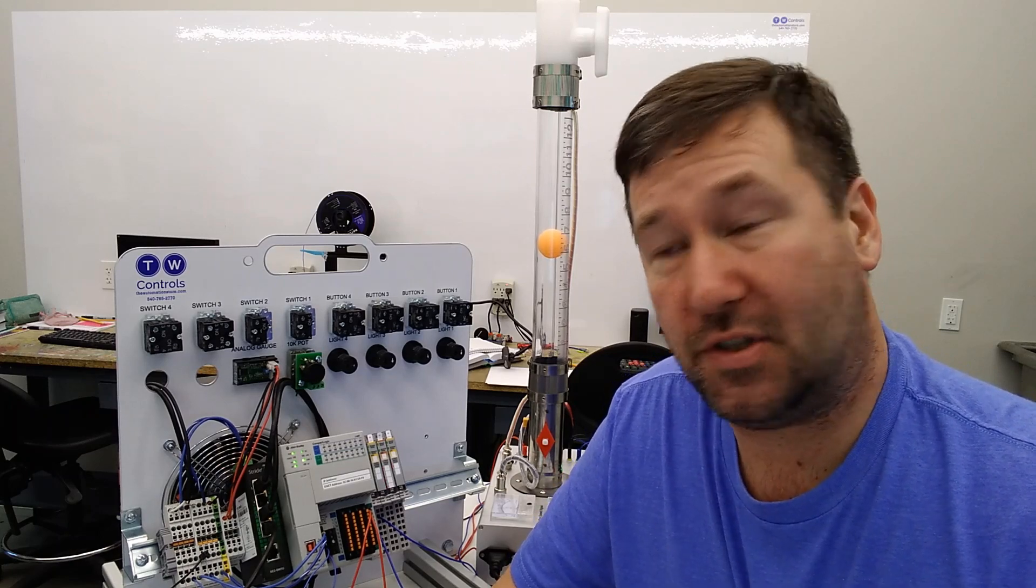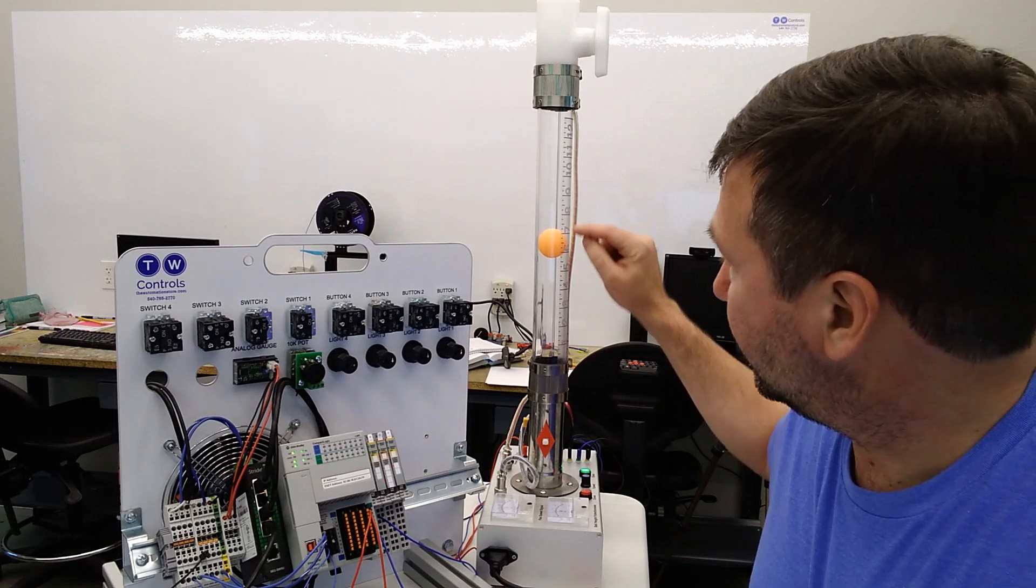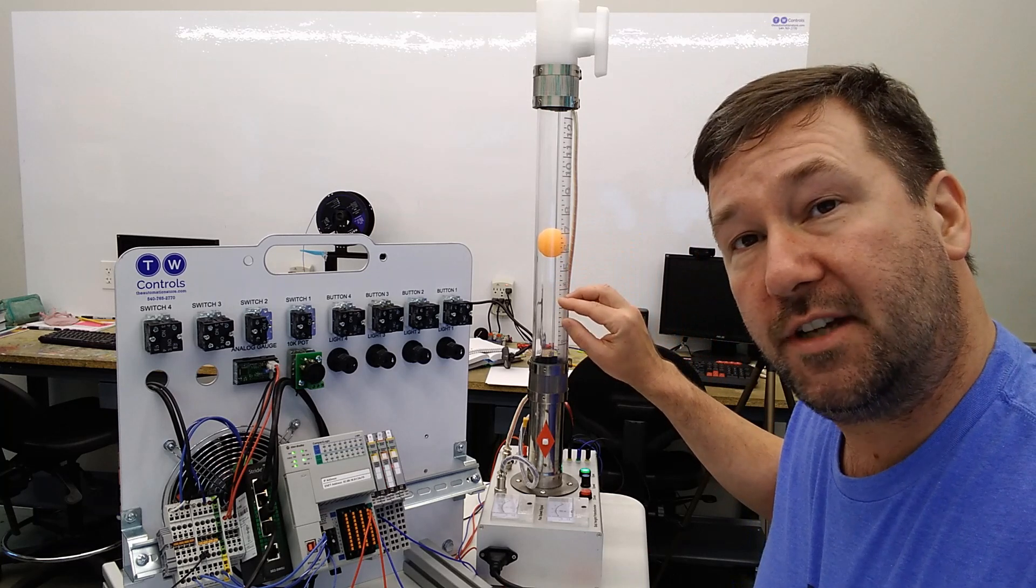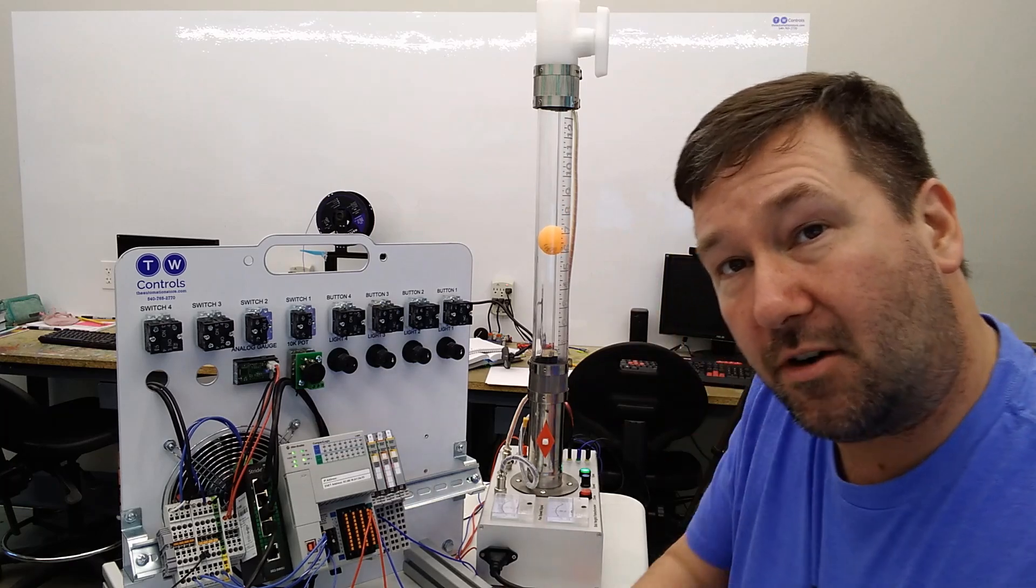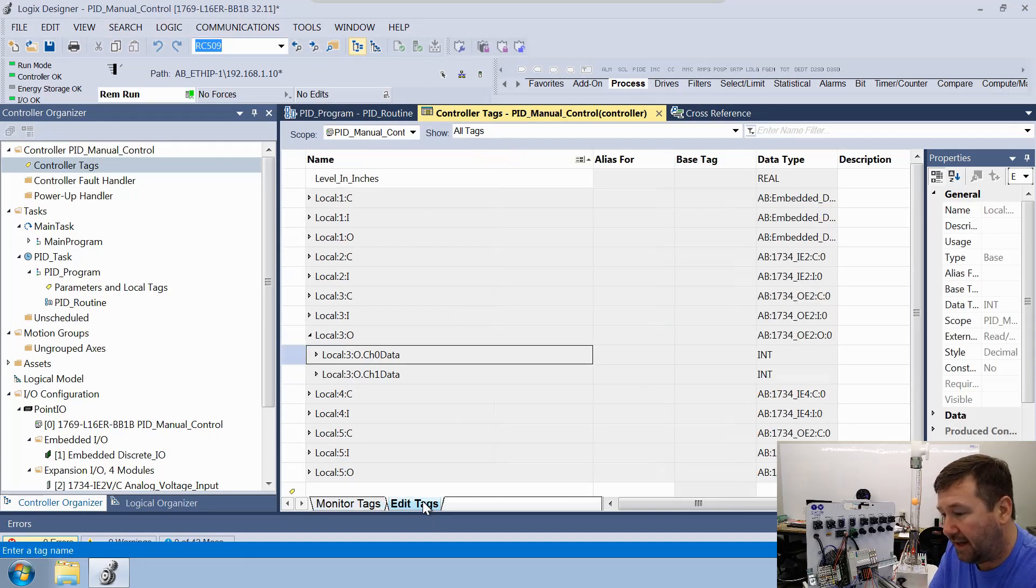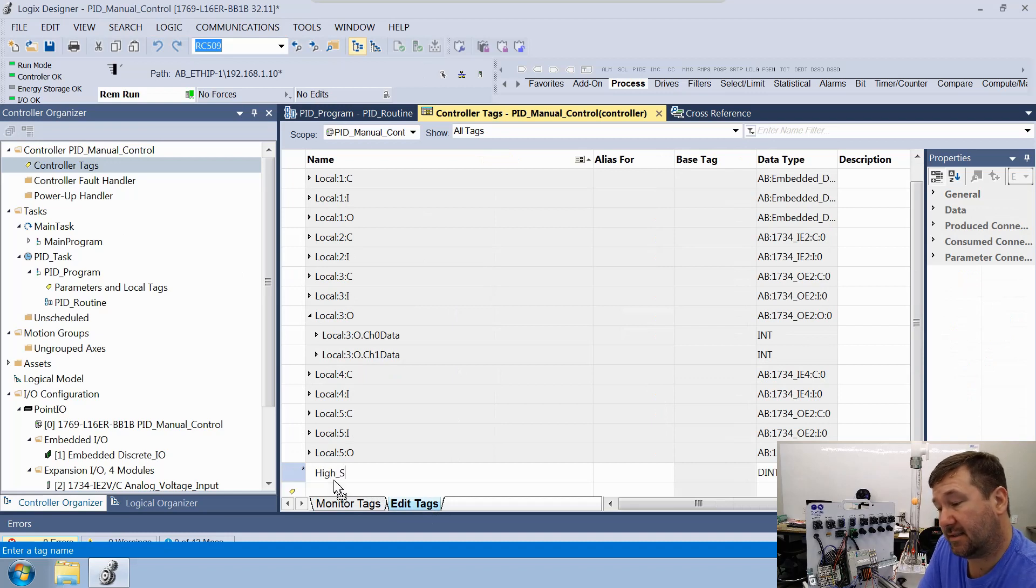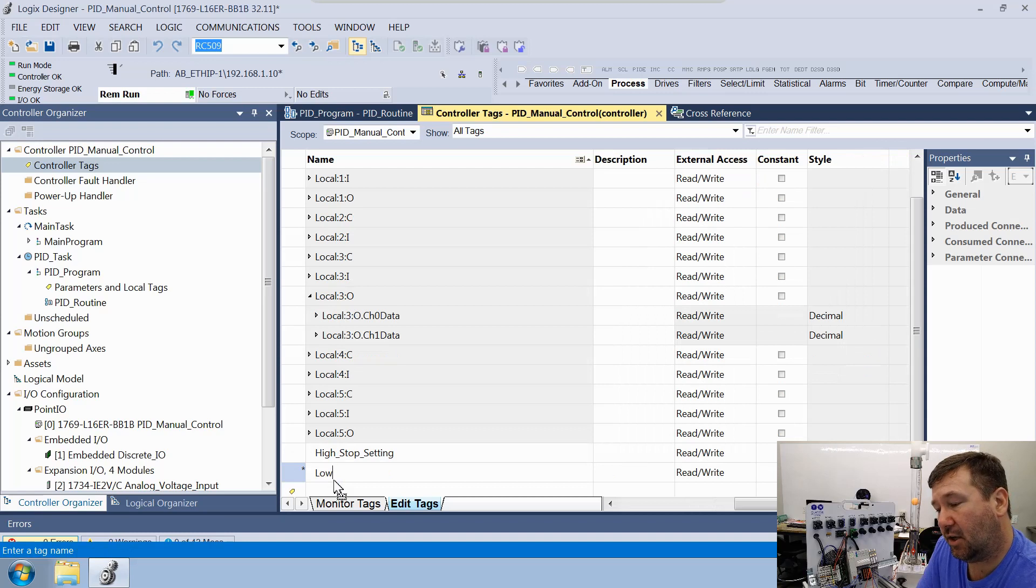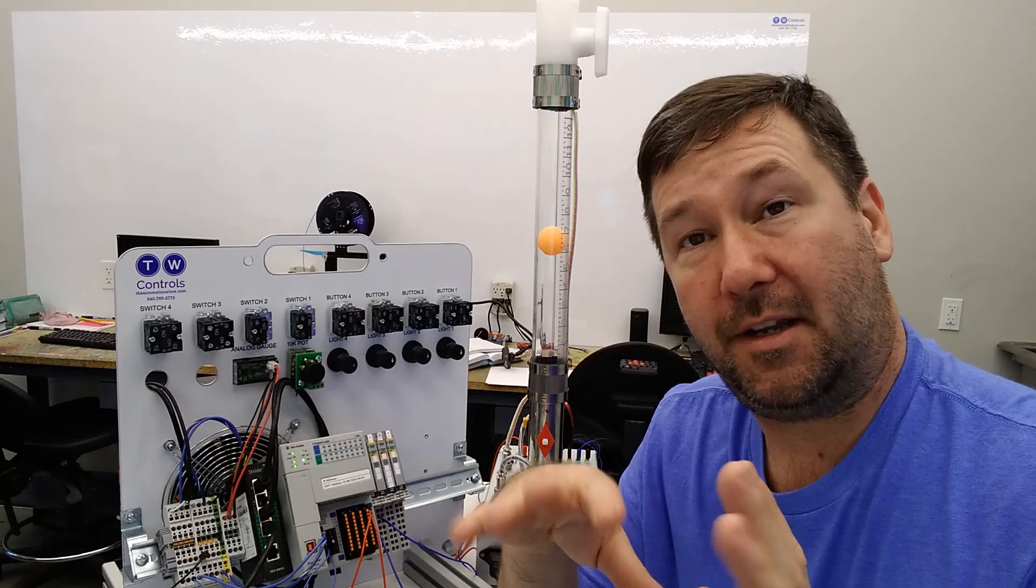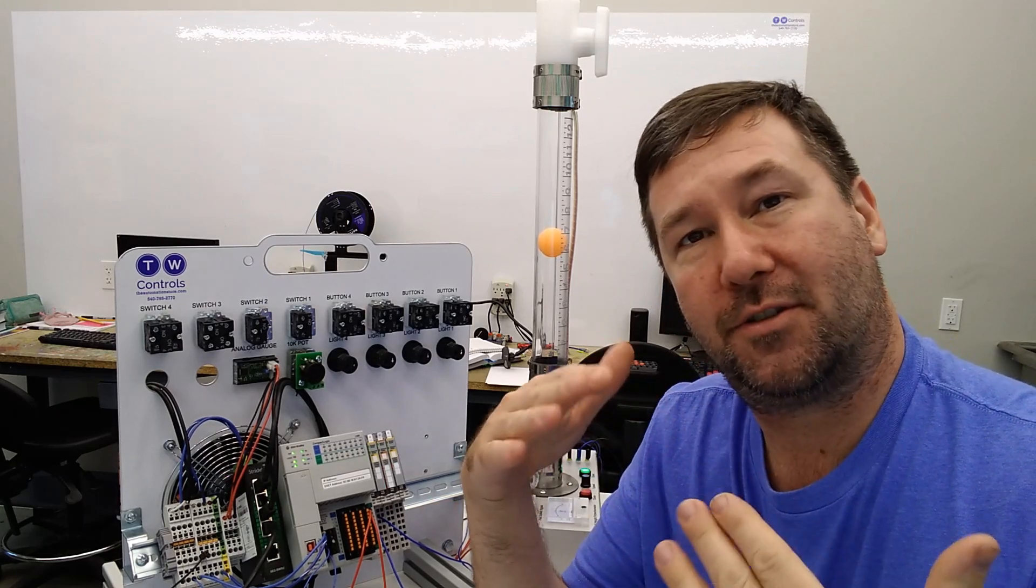Now what we want to do is, let's say we want this to turn on wide open when it drops below four inches. And we want it to run until it goes up to eight inches. That's where we're going to start at with this. Let's create a few variables for this. That way we can change it on the fly. We're going to go to edit tags. Let's start with a high stop setting, and that's going to be a real. Then we're going to have a low start setting, which is also going to be a real.